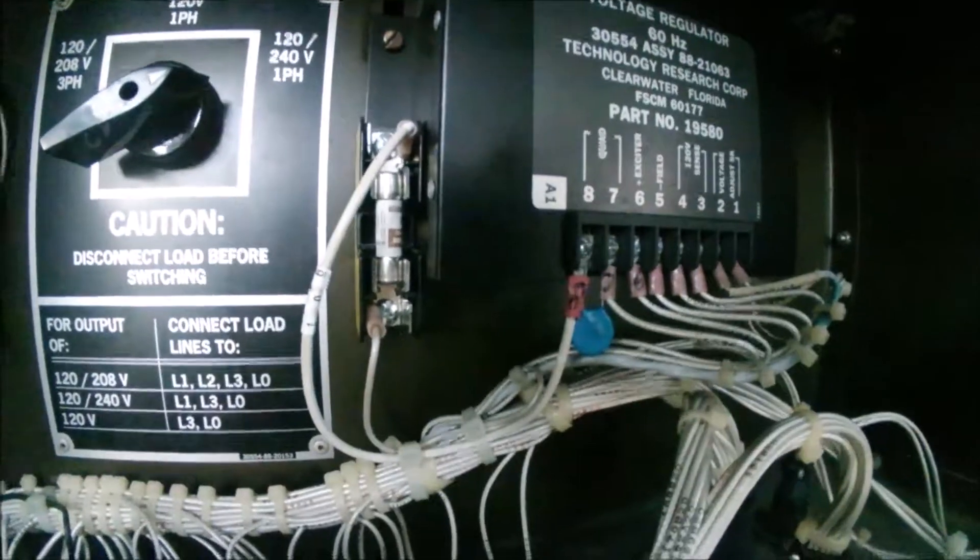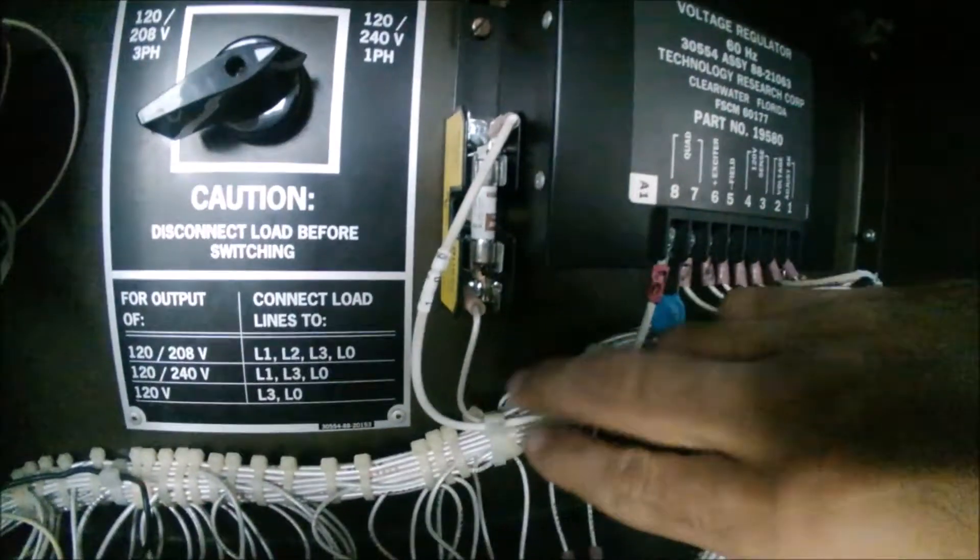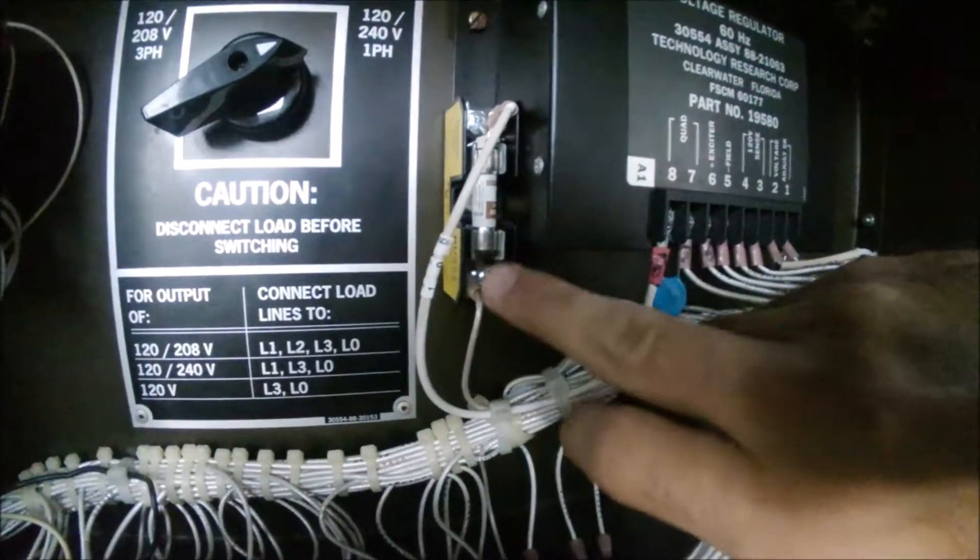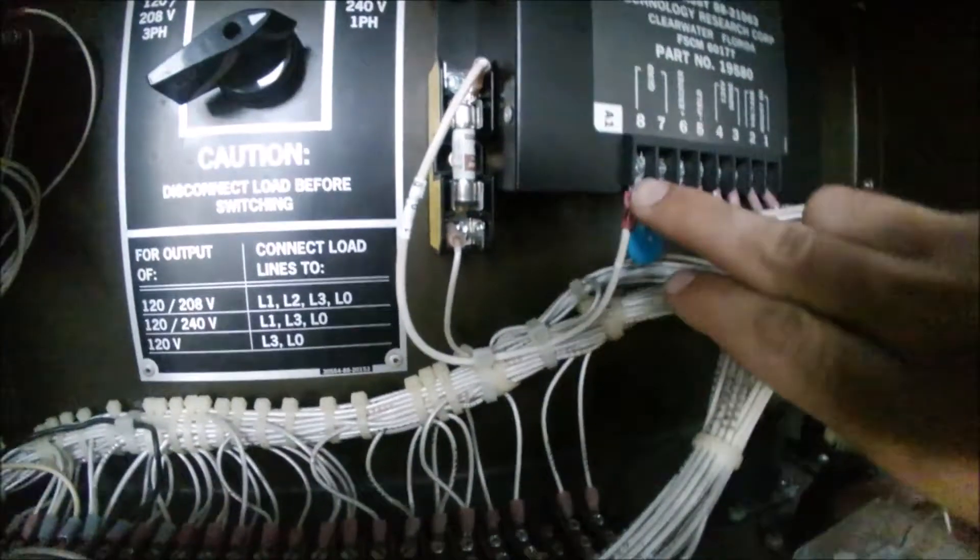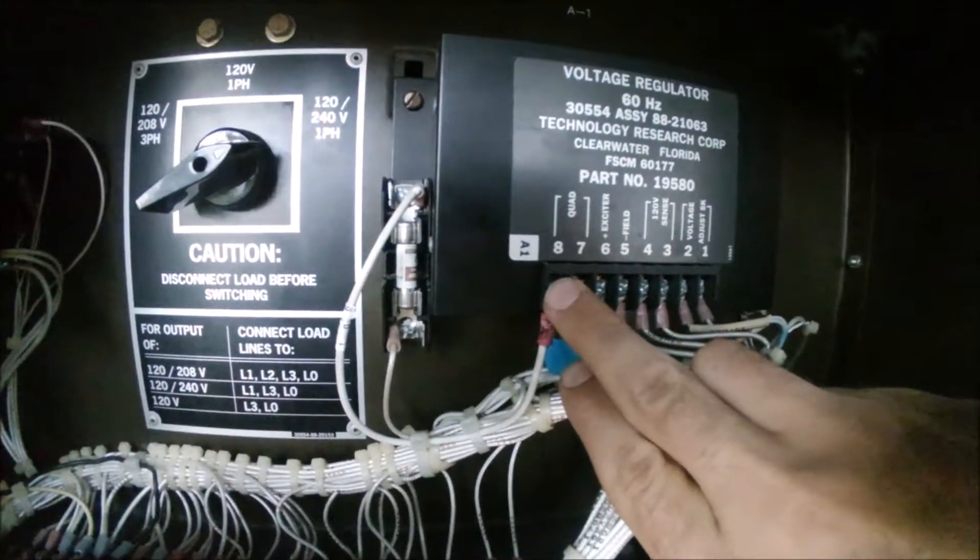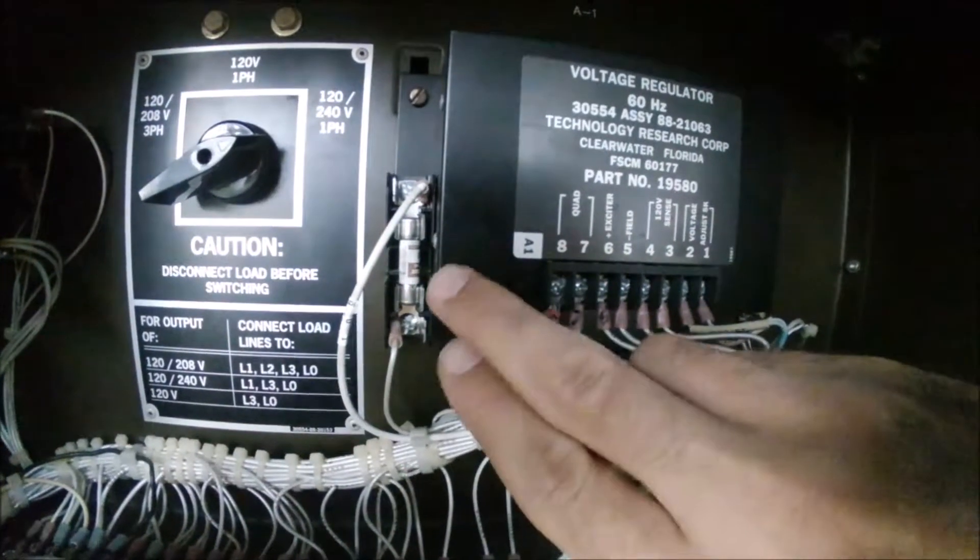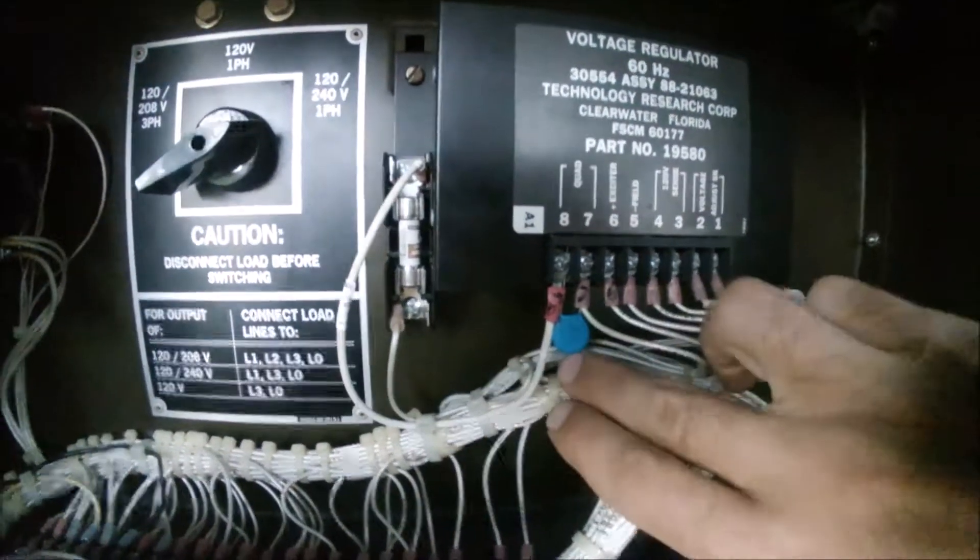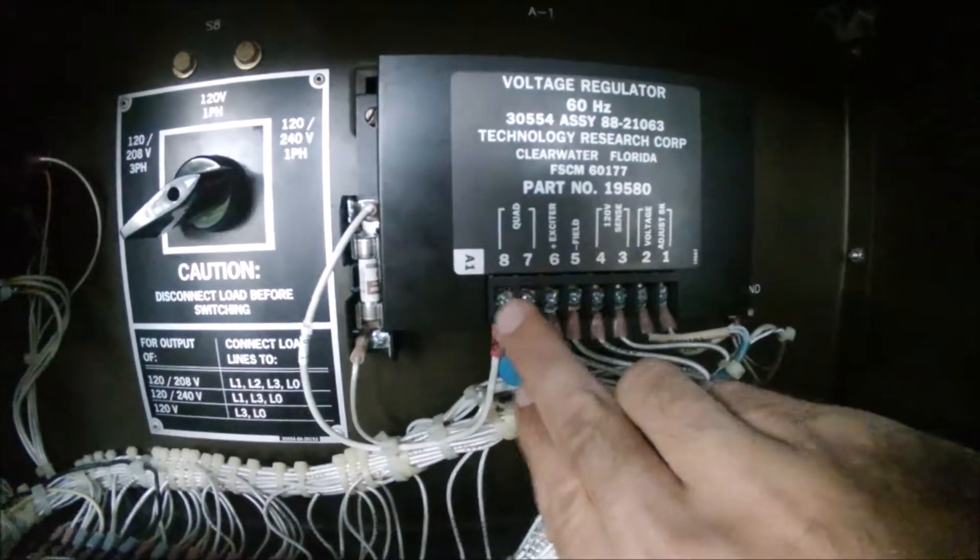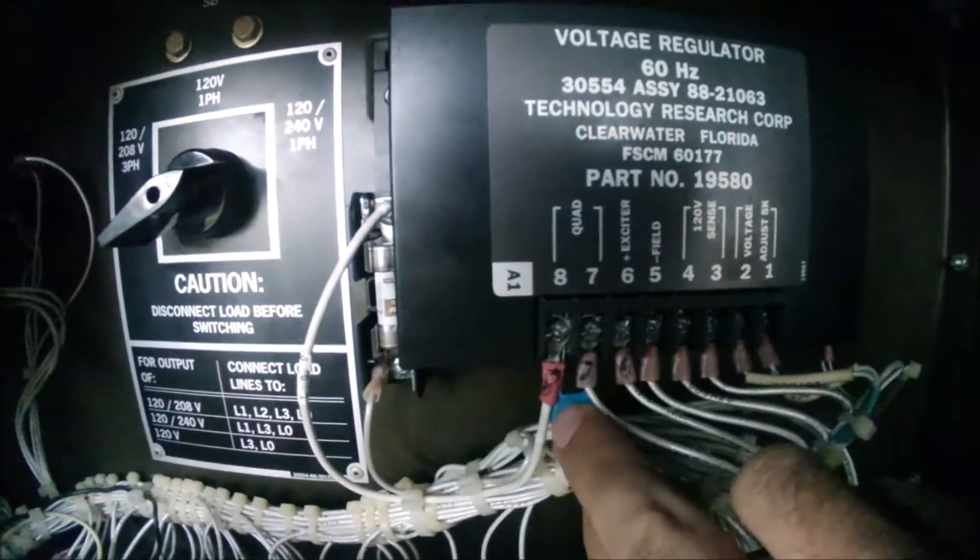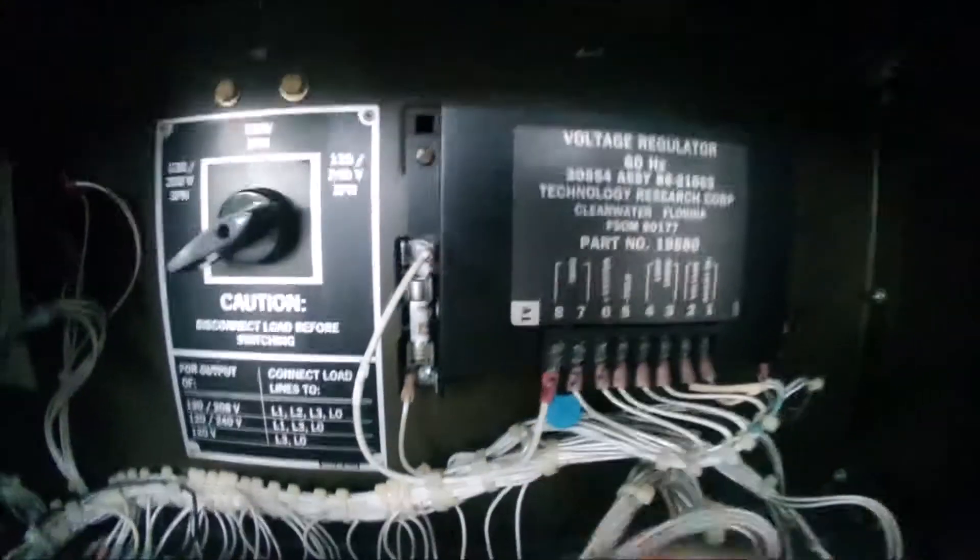Let me splice in real quick—I forgot to explain how this is installed. This is your wire right here on the outgoing side of the fuse that originally was connected to terminal 8. You make a little jumper from 8 to the top of the fuse and attach it. Then the varistor goes between terminals 8 and 7. For your connections, loosen them, stick the two poles on each side, and tighten them back down.